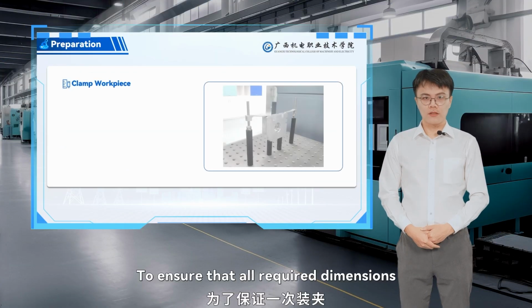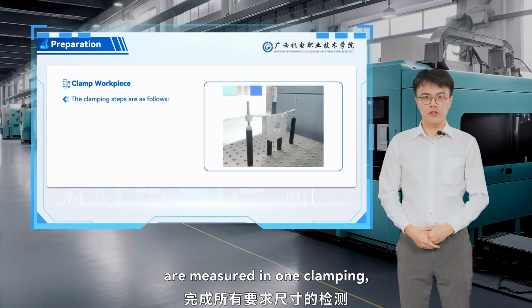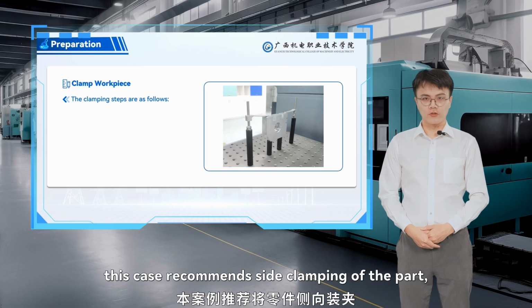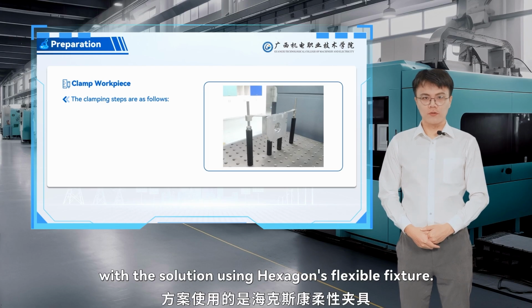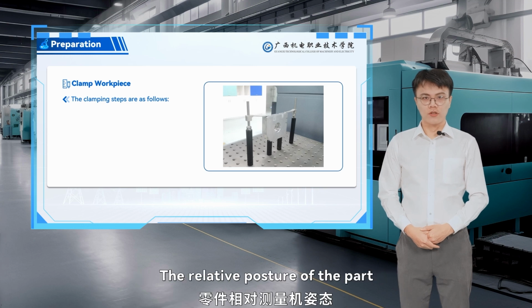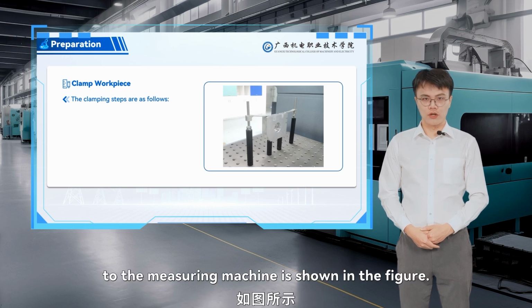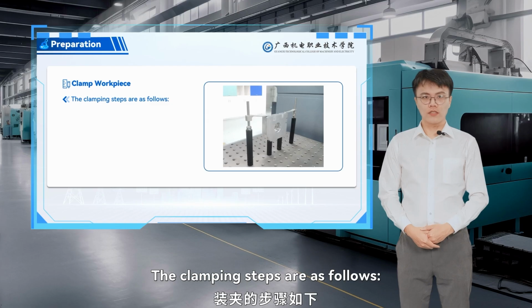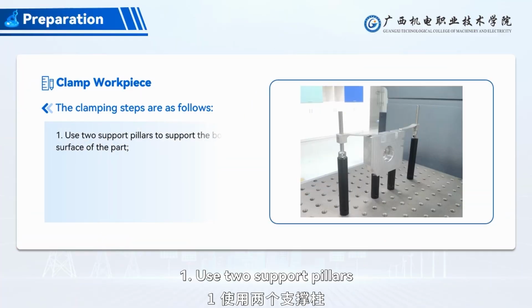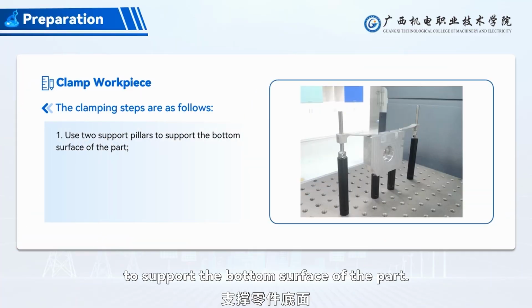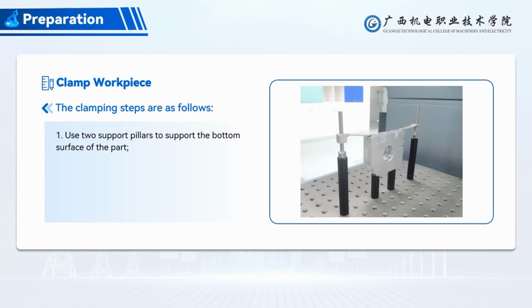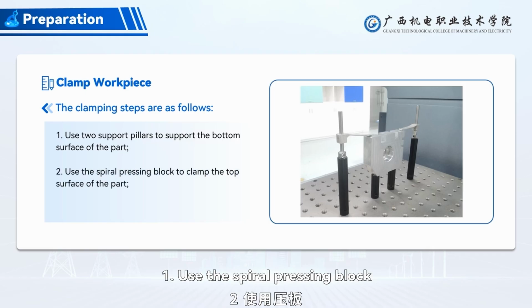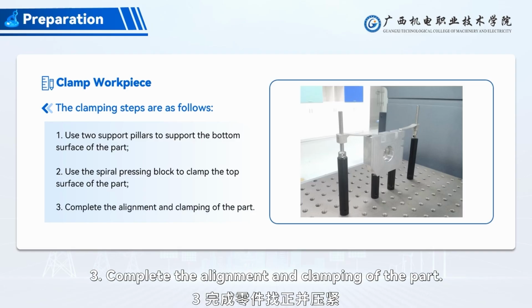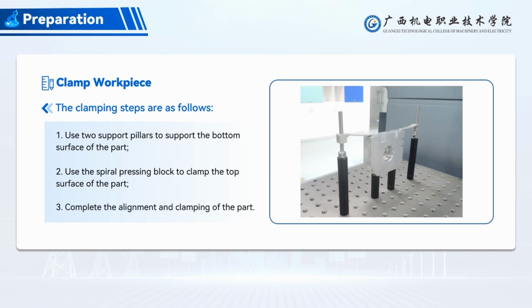Next is the part clamping. To ensure that all required dimensions are measured in one clamping, this case recommends side clamping of the part, with the solution using Hexagon's flexible fixture. The relative posture of the part to the measuring machine is shown in the figure. The clamping steps are as follows. 1. Use 2 support pillars to support the bottom surface of the part. 2. Use the spiral pressing block to clamp the top surface of the part. 3. Complete the alignment and clamping of the part.